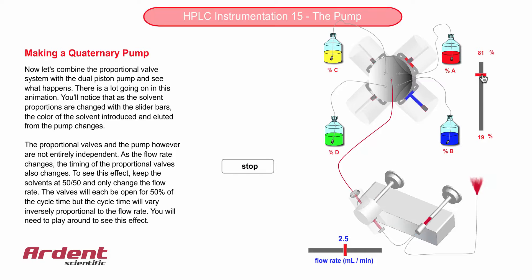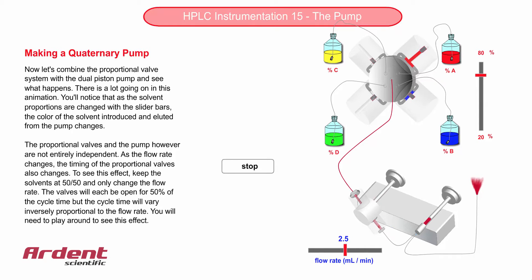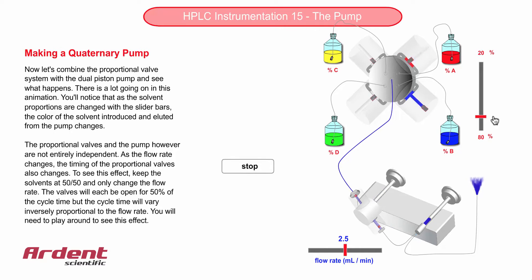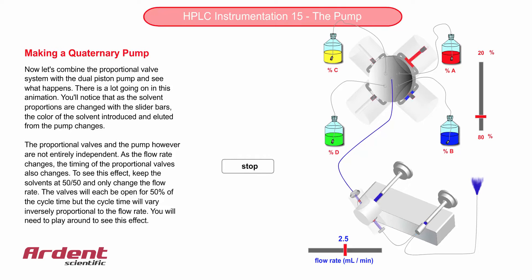You'll notice that as the flow rate changes, the cycle time of the proportional valves also changes. A lower flow rate correlates with a higher time to complete each stroke, and therefore a higher cycle time. To see this effect in action, keep the solvent mix at 50-50 but change only the flow rate.